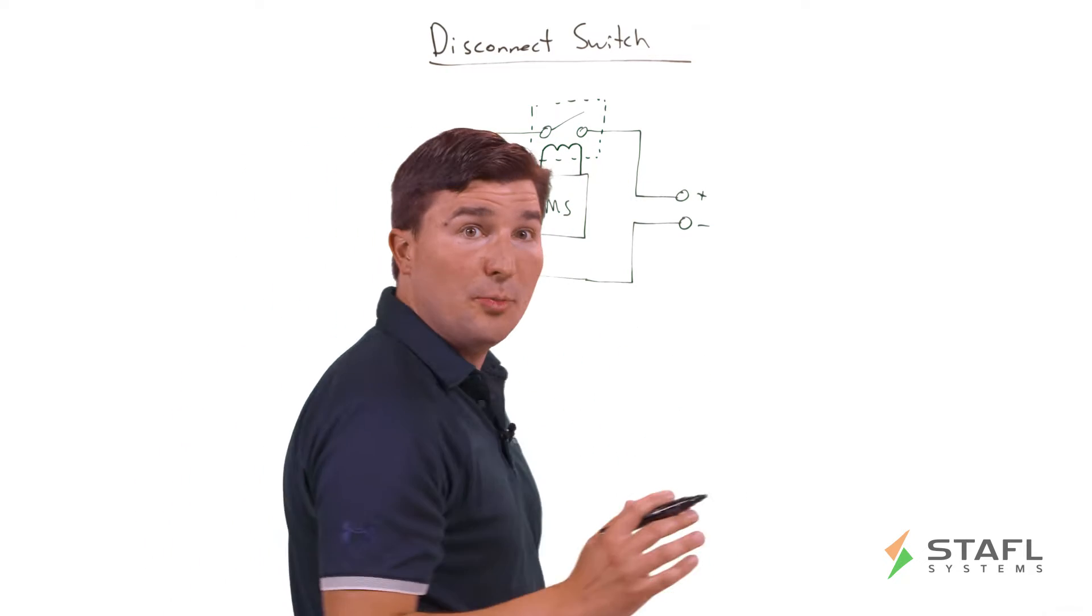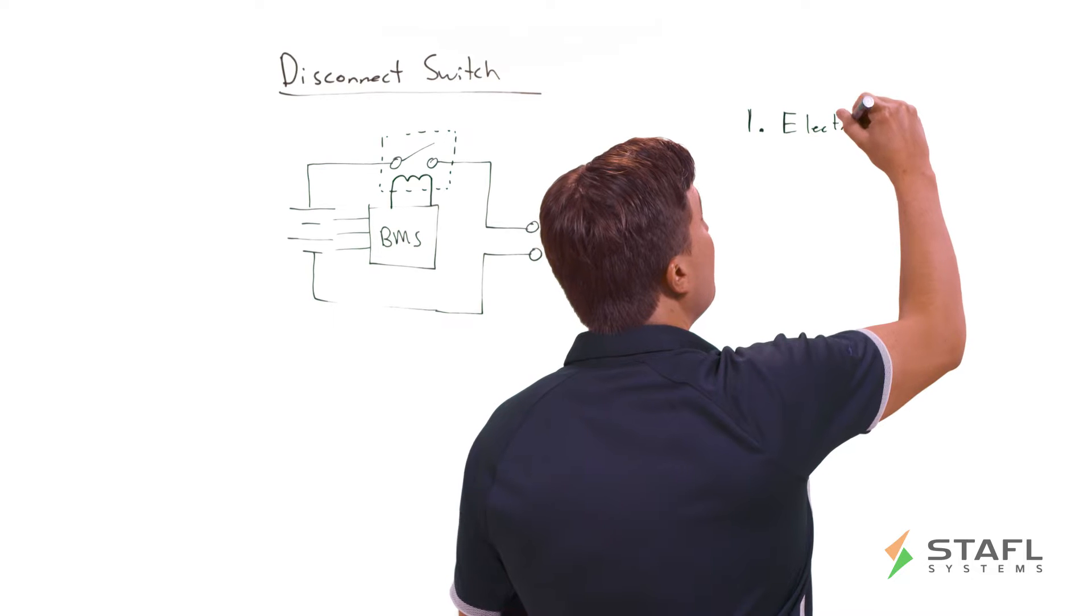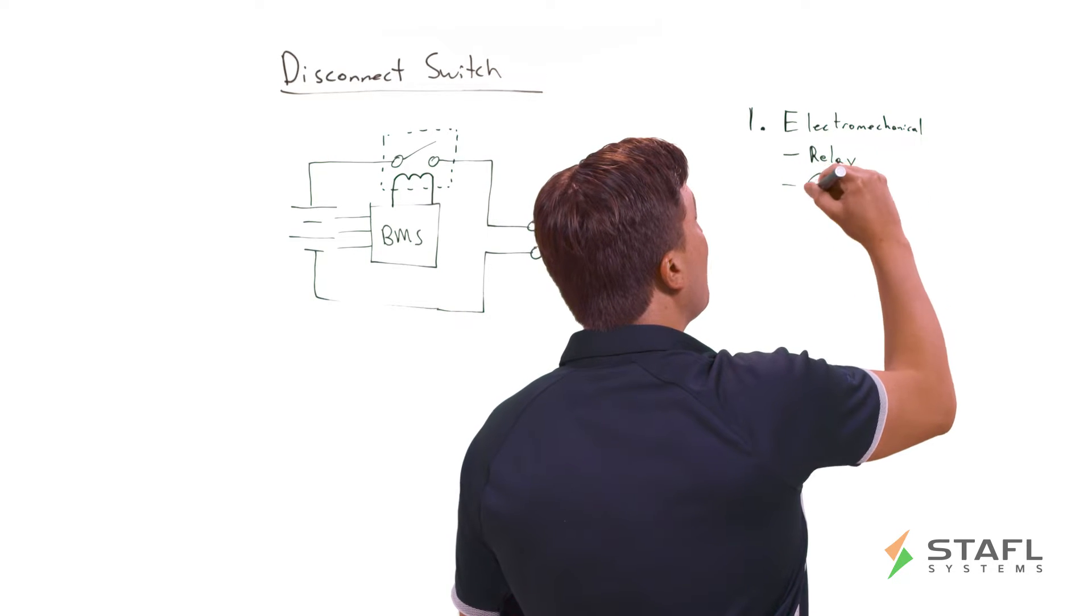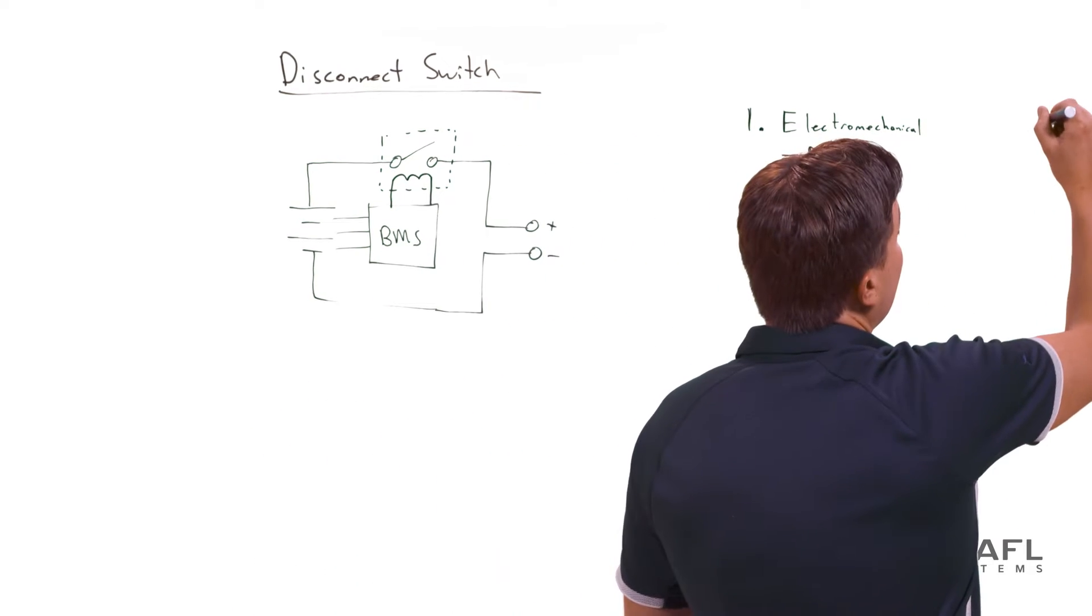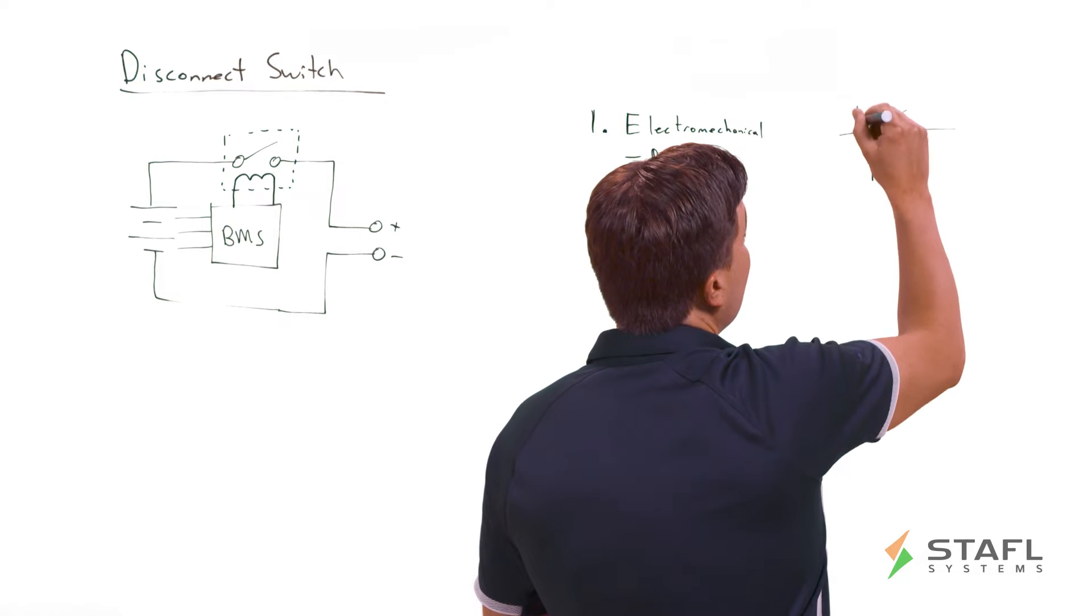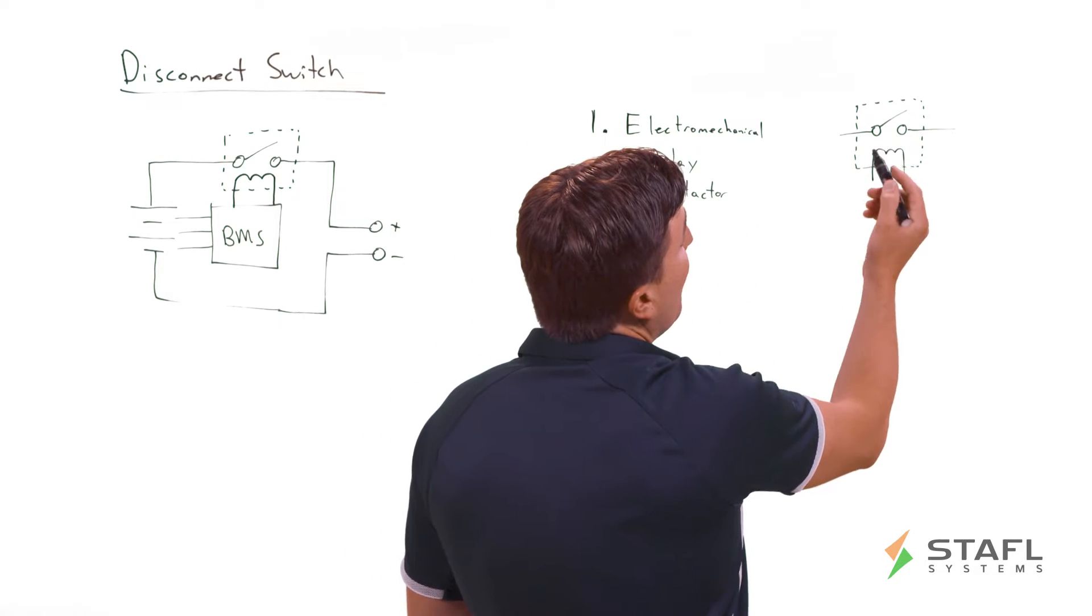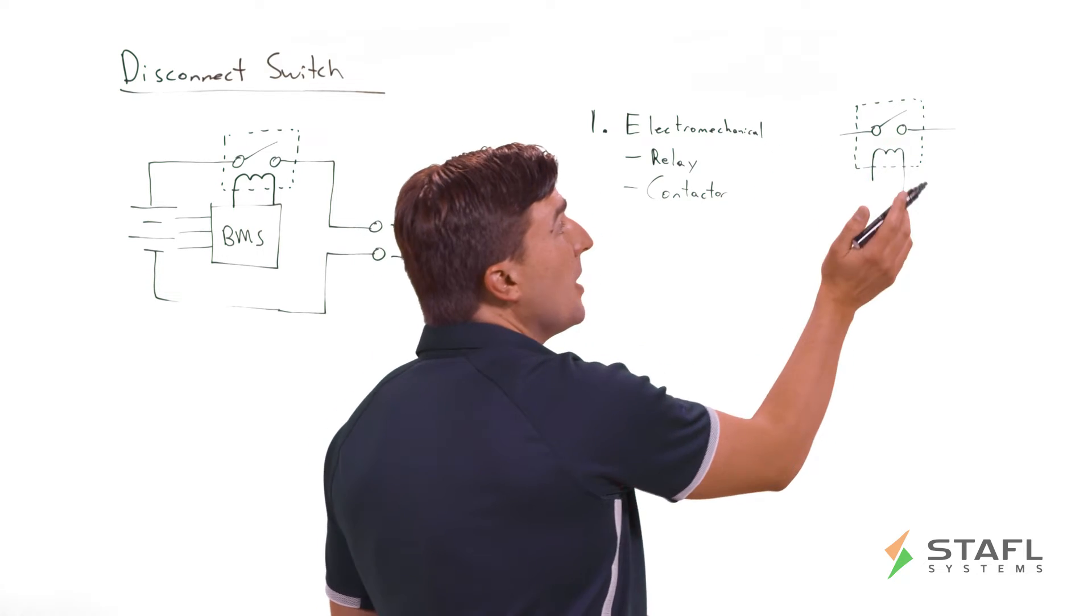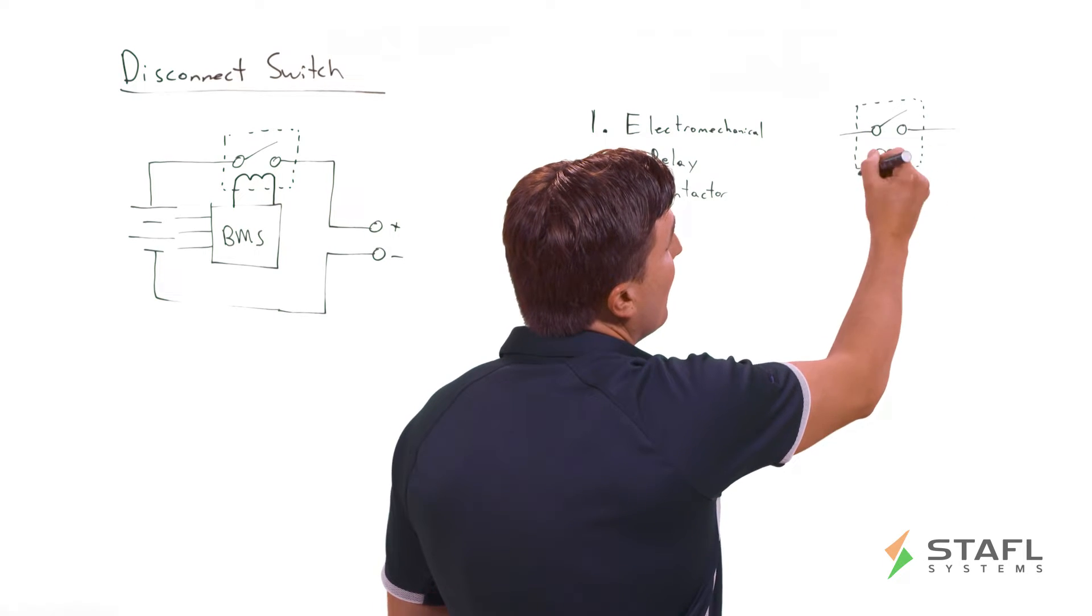Let's discuss the two primary types of disconnect switches. The first is electromechanical. This could be a relay or another term is a contactor. Diagrammatically, a contactor has two high current contacts and then an electrically isolated coil, which can determine whether this switch is closed or open. Closed would be for current flowing and open would be to interrupt all the current flow.